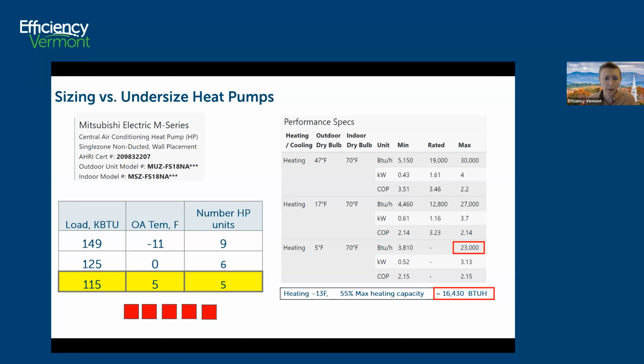Maybe kind of roll through, so where we left off was, if you were to air seal and insulate your building at -11, you would need 149,000 BTUs. That's 9 heat pumps. Then if you were to size only for 0, you could get down to 6 heat pumps. If you were to size for 5, you would only need 5 heat pumps.